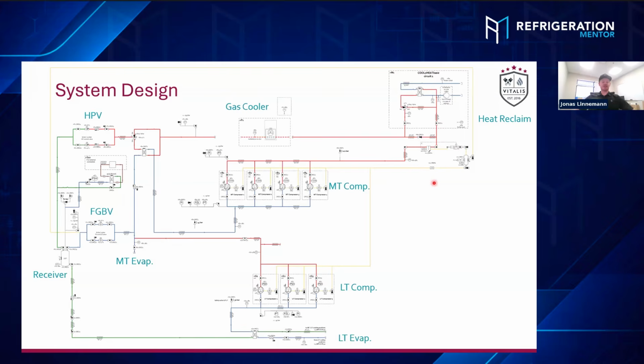Sometimes it's just easier to understand if you want to isolate whatever section for service or maintenance. It's sometimes much easier to just chase that down in the P&ID and identify the isolation valves or what strainer to change. That makes it sometimes easier to work off the P&ID. Sometimes it's just easier to find the root causes of issues on site by chasing the lines back to valves. And obviously, listening to components is sometimes very helpful. Touching, that's the real technician world. It's touching, feeling temperatures, and listening to components.